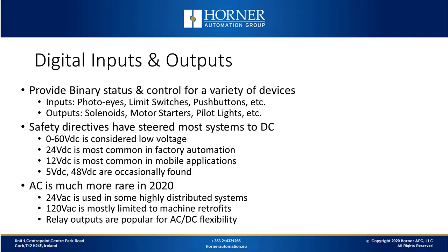Over the years, safety directives have steered most systems to DC voltages. Zero to 60 volts DC is considered low voltage and is considered the safest. The most common voltage used in factory automation is 24 volts DC. 12 volts is the most common in mobile applications. AC is much rarer nowadays from the standpoint of control voltages. 24 volt AC is used in some highly distributed systems, and 120 volts AC is mostly limited to machine retrofits. Relay outputs are very popular today because you can drive either AC loads or DC loads with those particular devices.